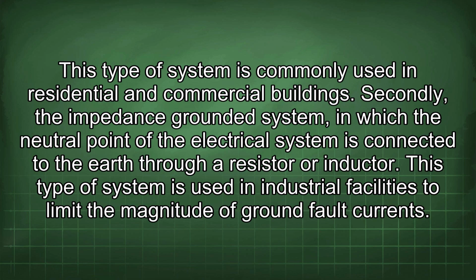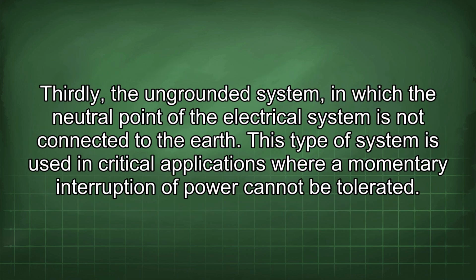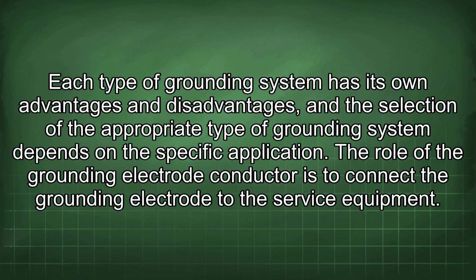This type of system is used in industrial facilities to limit the magnitude of ground fault currents. Thirdly, the ungrounded system, in which the neutral point of the electrical system is not connected to the earth. This type of system is used in critical applications where a momentary interruption of power cannot be tolerated. Each type of grounding system has its own advantages and disadvantages, and the selection of the appropriate type of grounding system depends on the specific application.